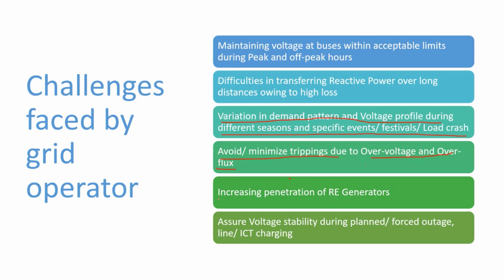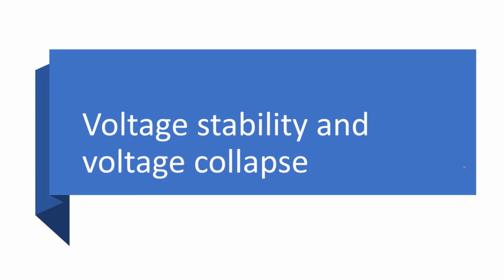And another thing is that with high RE generation, we will discuss the over voltage issue and the active power issue related with the RE generation. Just assume that there are issues where the pool of REs is getting connected. The fault level of that substation is low. The strength of that substation is low. So any fluctuation in reactive power at those places results in severe variation of the voltages. This is also a challenge for the operator, to maintain the voltages and to reduce this fluctuation in the system so that RE generators do not get impacted. So these are the challenges.